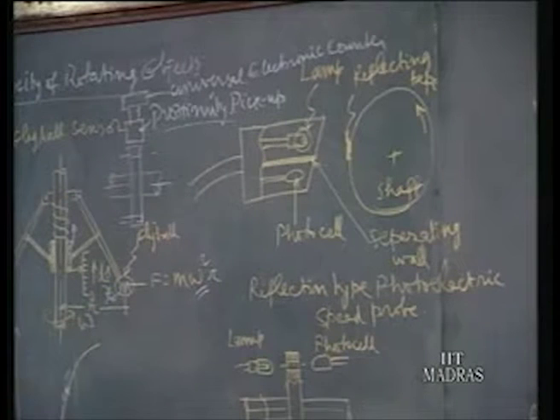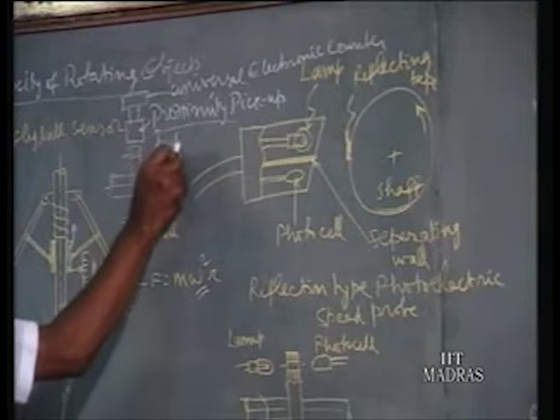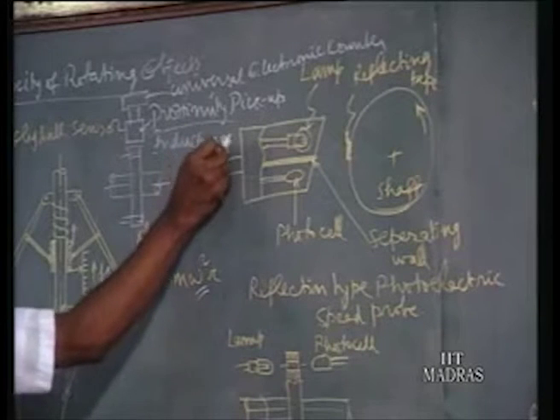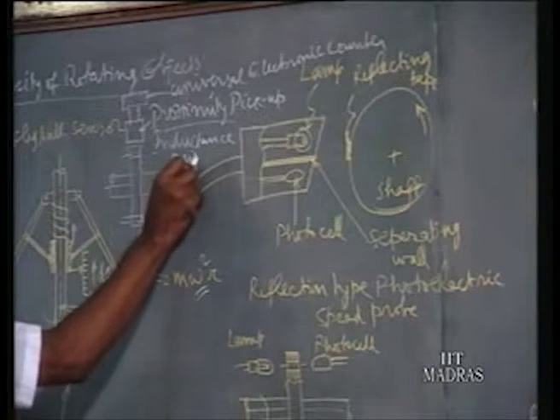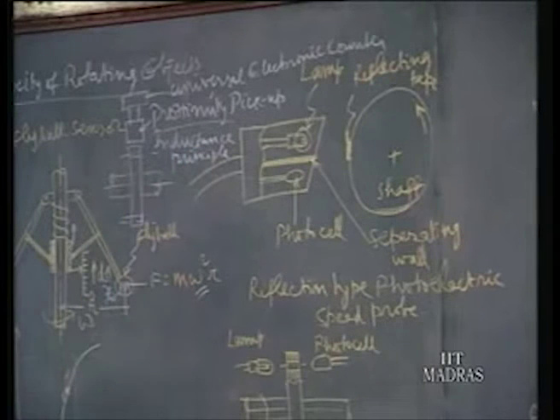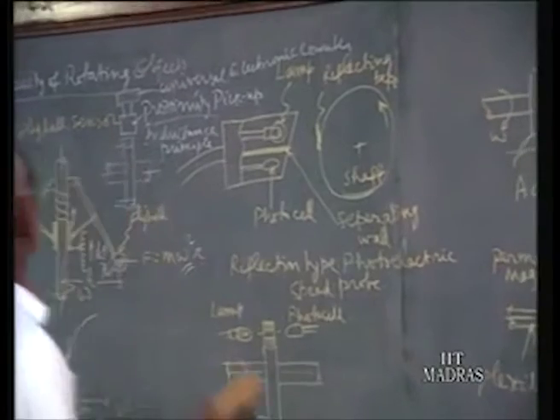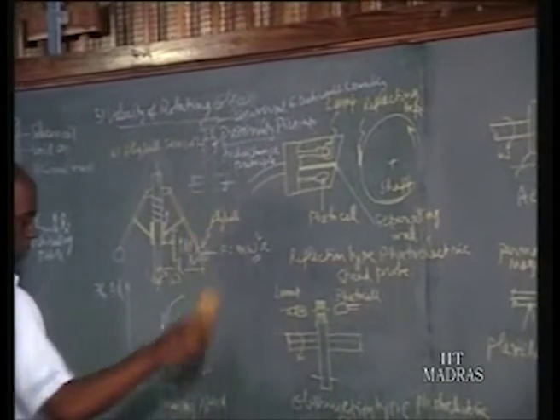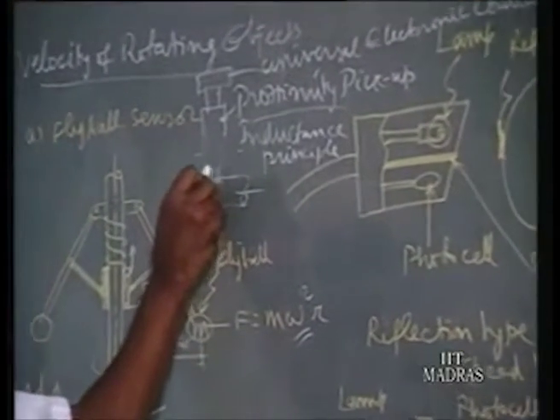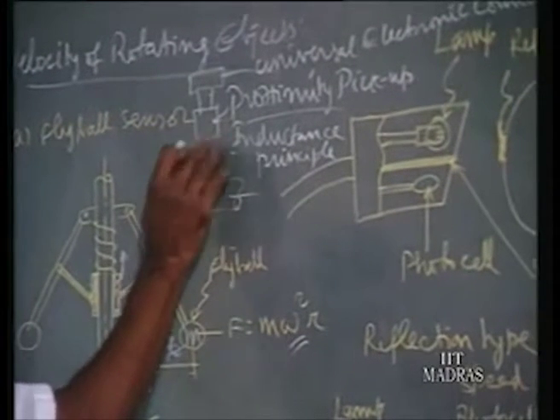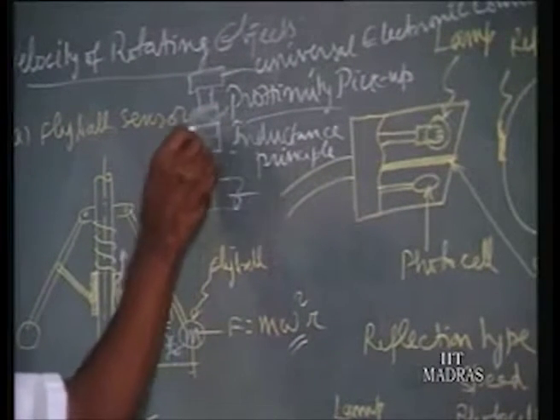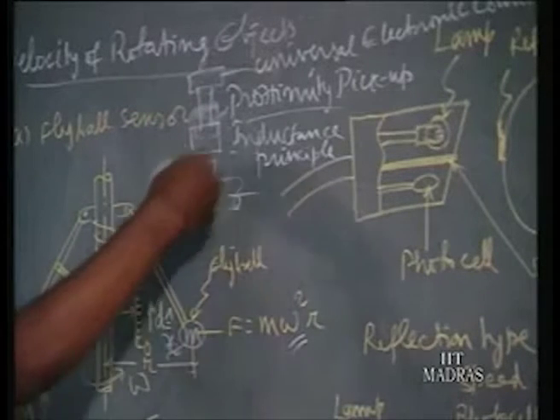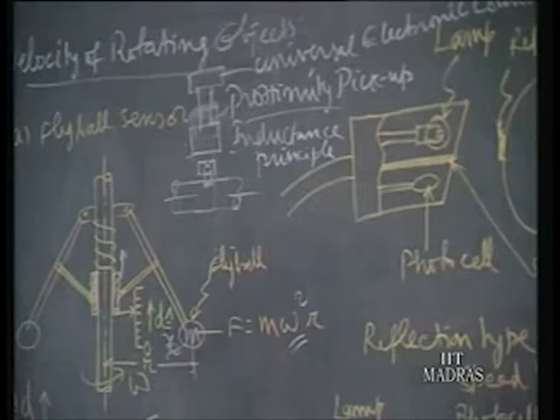That is the inductance principle. The inductance varies whenever a tooth comes. When you don't have any gear, what you can do is substitute the gear by a screw. The shaft is there, we can substitute it by a screw head, and now put your proximity pickup near the screw. Whenever the screw head comes in front of the proximity pickup, one pulse will be made.